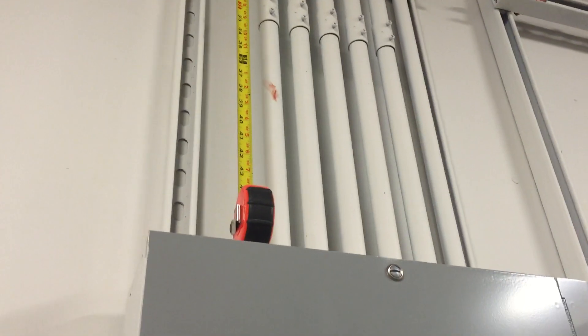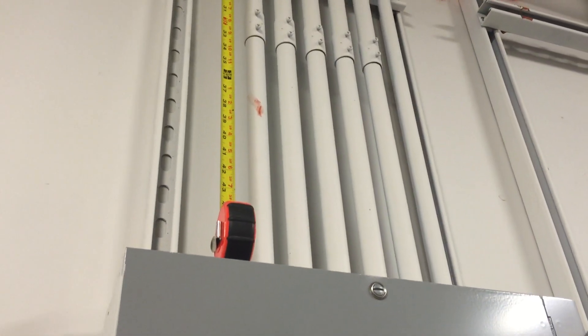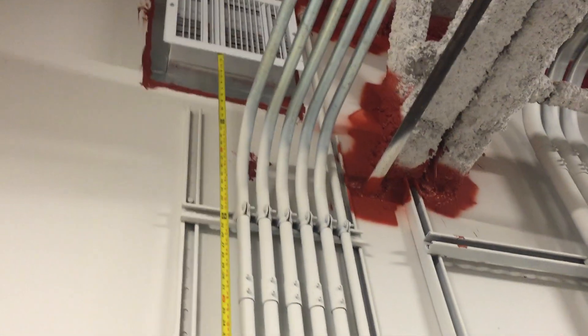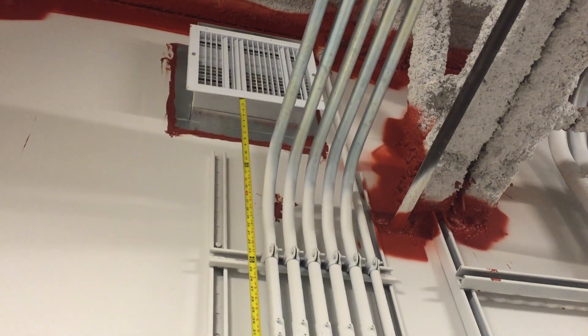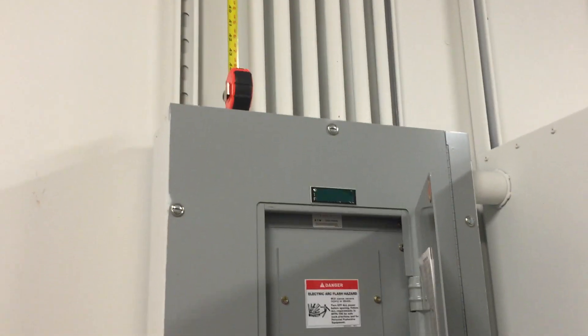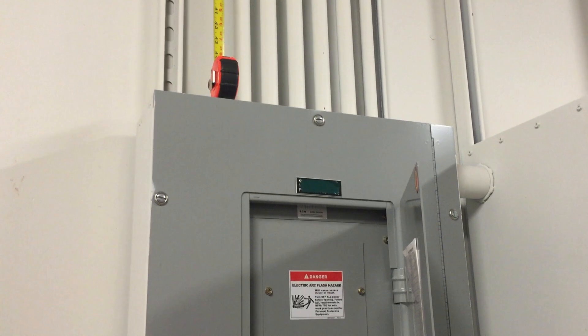That's going to leave installers less room to get pipes in or run cables. Also, if there's any moisture or condensation in that ductwork and it leaks out, that could end up right inside our panel board — that could be a really bad situation.